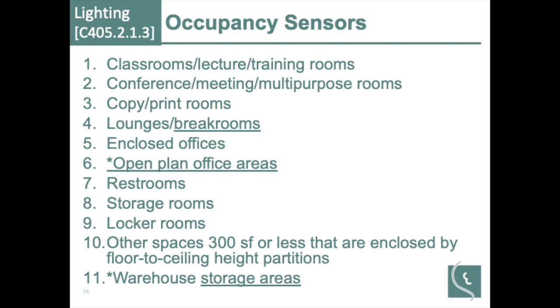But previously, open office plans like cubicle areas weren't included in that because they didn't want lights turning off on the whole area if someone was in the back of the room. So they've broken it up and required a sensor per so many square feet. I think it's 600 square feet. So those are the additions on the lighting sensor requirements for lighting. Everything else is the same as the 2015 code: classrooms, conference rooms, spaces with fluctuating occupancy.